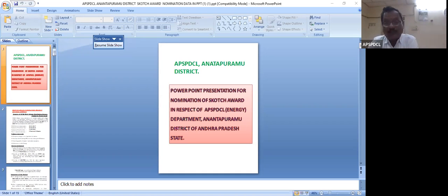In addition to that, 23,587 unauthorized services were also regularized by doing the HVDS system. Because of this high voltage system, LT voltage levels at consumer motor terminals have increased from about 360 volts to 415 volts. After implementing this, the failure rate of the existing 100 kVA and 63 kVA DTRs has drastically reduced from 6.63 to 1.51, sir.